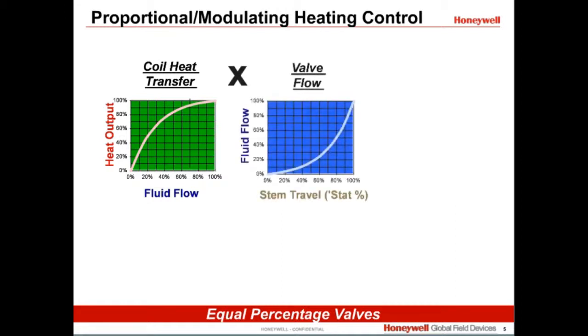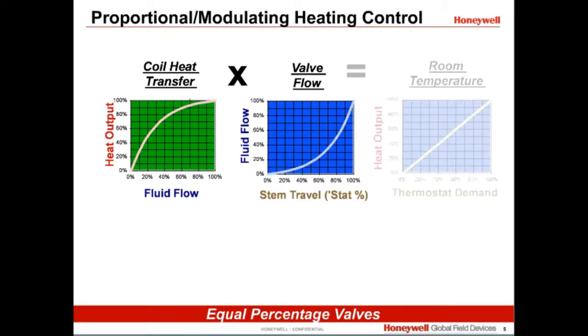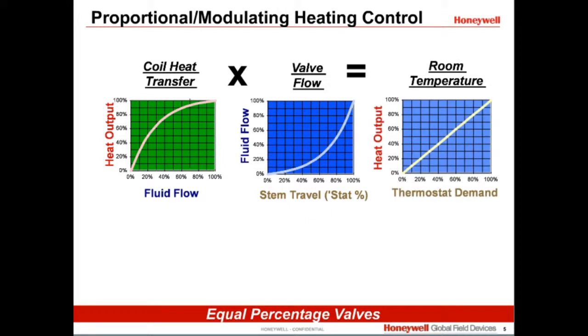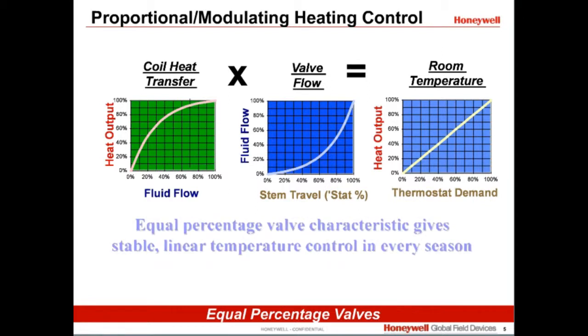A valve with an equal percentage flow characteristic only opens slightly in the first part of its travel, allowing only a small amount of hot water into the system. As you can see, when combined with the heat transfer of the coil, the net result is a linear heat delivery. This linear relationship creates optimal control and is more energy efficient and much easier to control accurately.